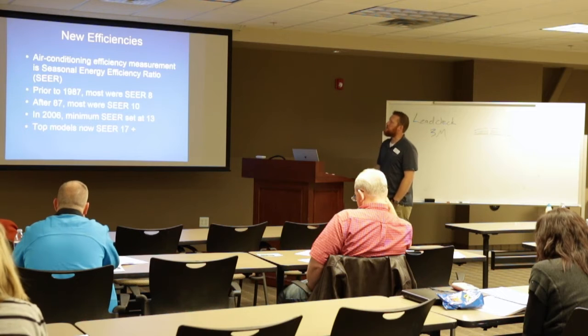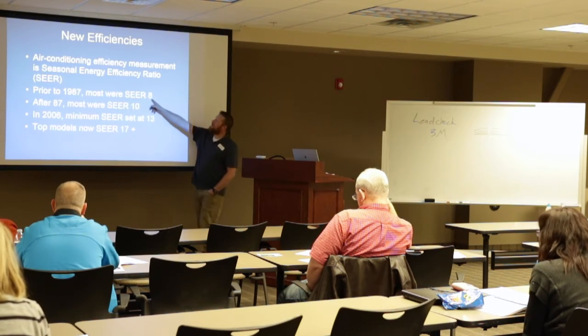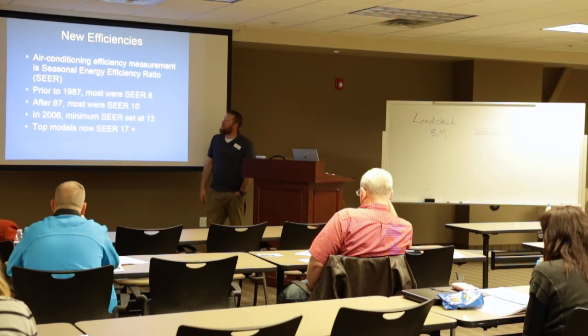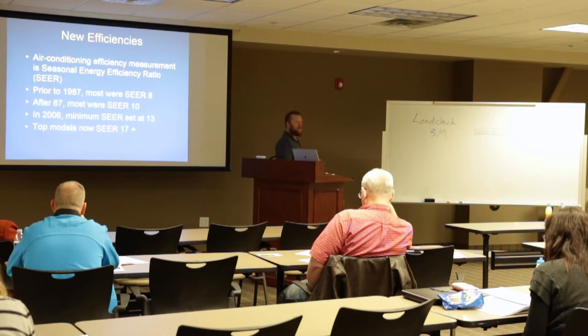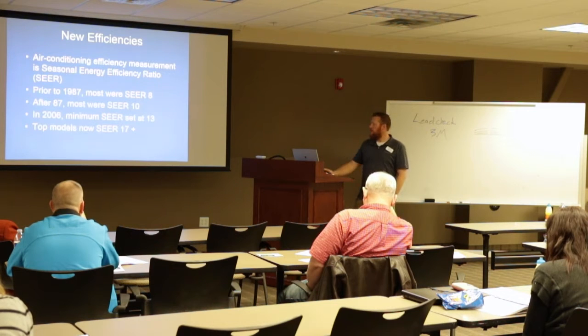Air conditioners and efficiencies are rated in SEERs. SEER stands for Seasonal Energy Efficiency Ratio. So you had about a SEER 8 prior to 87. Now we're seeing into the 17, even 19, closer to 20 SEER for some of your higher end air conditioners.